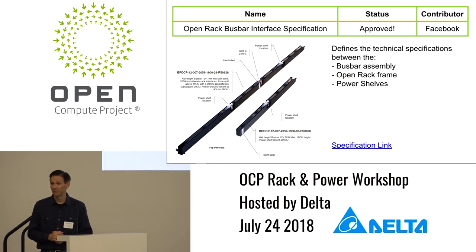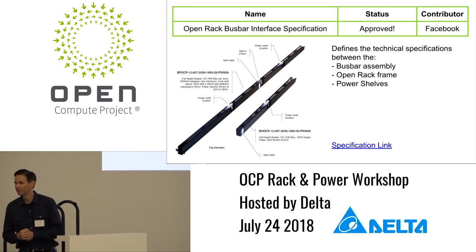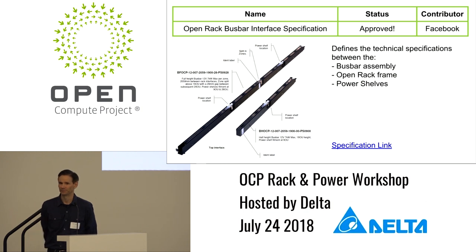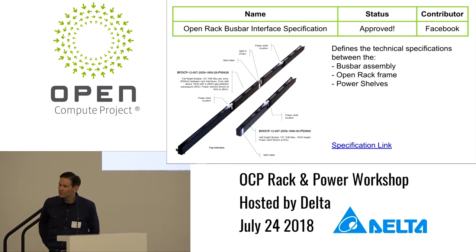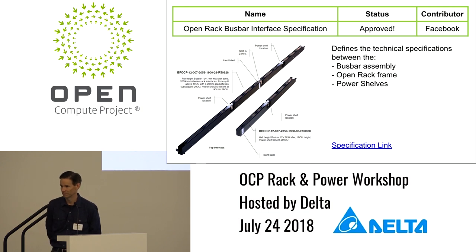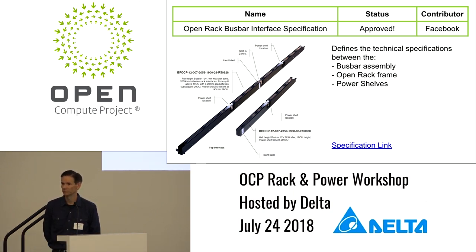Would it be lighter? Absolutely — there'd definitely be less copper for 48-volt. I think this is some of the motivation behind it. If you're going into a colo facility that has a six kilowatt cooling capacity, you'd probably get away with a lot less copper in the bus bar. The whole idea is that based on where that rack ends up, you match up the bus bar at the last possible instance — or make a final decision. Even within a facility, does it go into a four kilowatt white space or a 25 kilowatt white space? You can make that decision and install the proper bus bar.